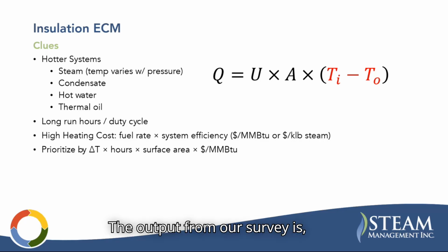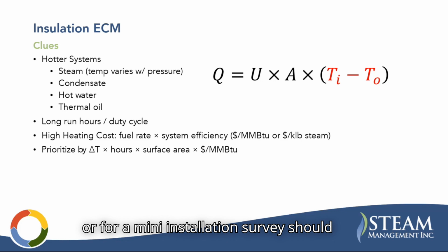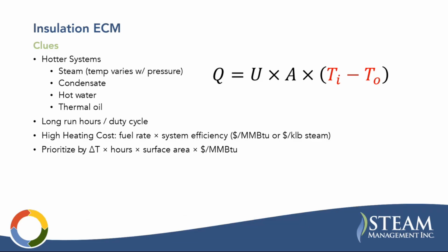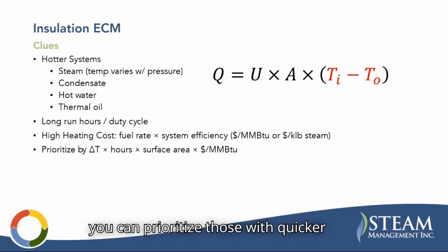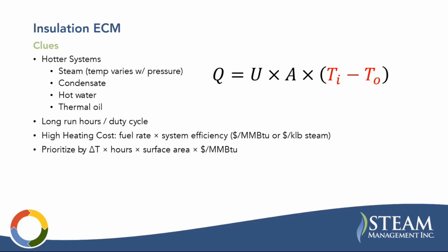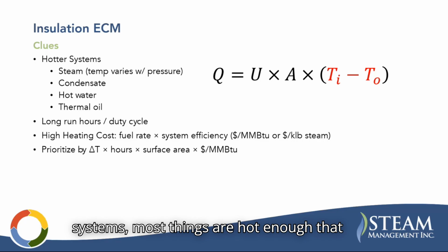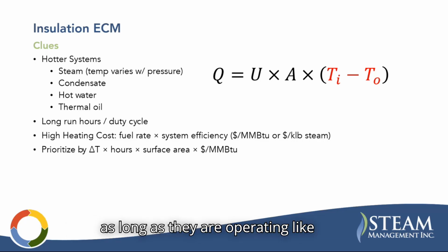So the output from our survey, or for an insulation survey, should be a line by line application schedule with the opportunities listed, and then you can prioritize those with quicker payback. So you don't necessarily insulate every single thing that was identified. Although in steam systems, most things are hot enough that as long as they are operating a significant amount of the year, it's going to have a decent payback.